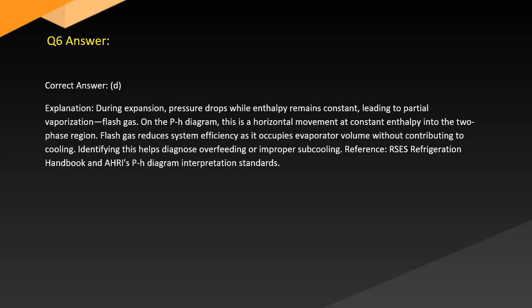Answer. Correct answer: D. Explanation. During expansion, pressure drops while enthalpy remains constant, leading to partial vaporization. Flash gas. On the P-h diagram, this is horizontal movement at constant enthalpy into the two-phase region. Flash gas reduces system efficiency as it occupies evaporator volume without contributing to cooling. Identifying this helps diagnose overfeeding or improper subcooling. Reference: RSES Refrigeration Handbook and AHRI's P-h diagram interpretation standards.